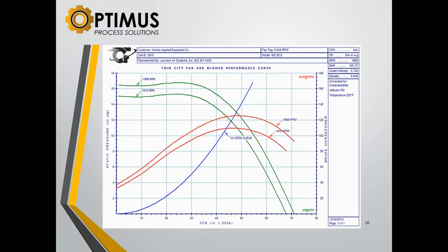Right. You can think of it in two ways. One is a material handling system, the other as an air system. And it makes a lot of sense if you think of it in terms of part of the air system. What can happen is you may say, I have gas coming out of the dryer at 230 degrees, at a specific altitude, and most of the people who would provide the fans for these systems can take that information, plug that into a typical fan selection chart, and they can make a real nice selection and generate a curve.